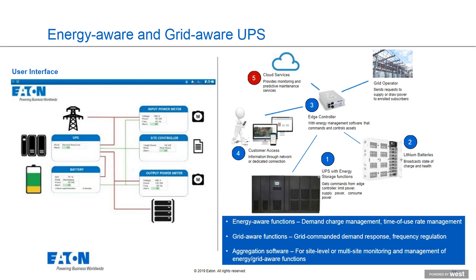On the right-hand side of the display you have power metering: how much power am I drawing from the utility right now, and how much am I putting out? Look at the bottom, there's the output power meter. If I'm putting out 200 kilowatts, I'd expect to draw in a little more than 200 kilowatts on the input. But if set up as a distributed energy resource, a command could come from the user or the utility company as a request, and the UPS goes into EnergyAware mode and begins to draw off its battery. There's a target input power.